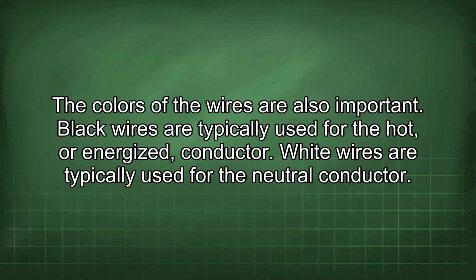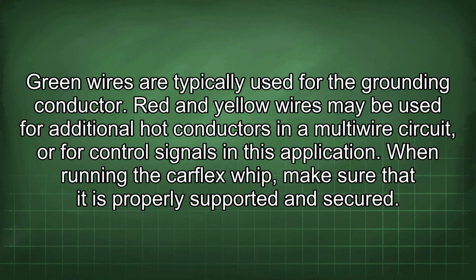The colors of the wires are also important. Black wires are typically used for the hot or energized conductor. White wires are typically used for the neutral conductor. Green wires are typically used for the grounding conductor. Red and yellow wires may be used for additional hot conductors in a multi-wire circuit or for control signals in this application. When running the carflex whip, make sure that it is properly supported and secured.